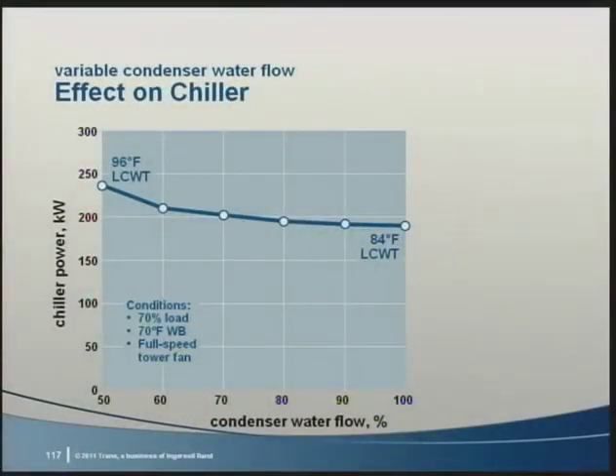Now, since the tower entering water temperature is the same as the chiller leaving condenser water temperature, we can look at the chiller power at these same conditions. At the same chiller load, as the water temperature leaving its condenser rises, so does chiller kW. Now, if we just look at chiller kW, we'd never reduce the condenser water flow rate. But we need to add the cooling tower fan kW, the pump kW, and the chiller kW so we can see how the system operates. Remember, this is one snapshot in time, 70% load and 70-degree wet bulb. We'll look at a few others in a second.